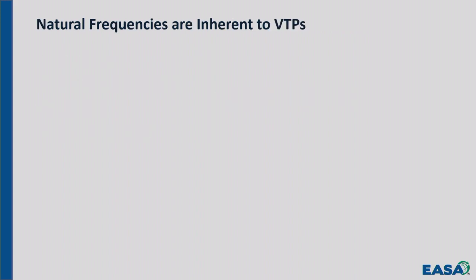Obviously, the vibration issues on vertical turbines and pumps and their motors are most often related to natural frequencies and what we call resonance. A natural frequency is, if I give this thing a little shake, I don't know if you can see this whole thing up here shaking. If I give it a little bump, my computer screen is bouncing back and forth. I'm getting a little seasick from watching it after the third presentation. That's a natural frequency. If you bump something and it vibrates at some frequency, that's a natural frequency.